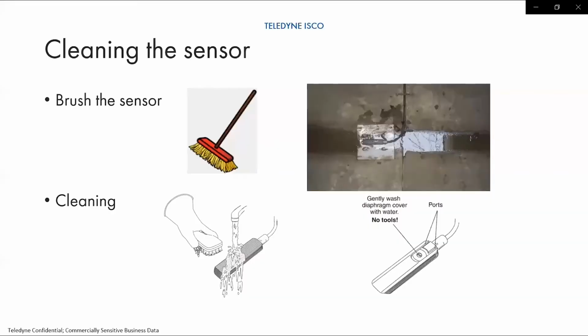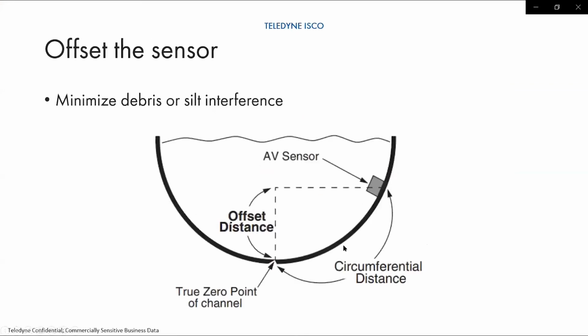Other cleaning techniques, I see a lot of field crews essentially go out with a broom, or they fabricate a pole and put a broom head on there and just simply brush off the top of the sensor to clean that debris out of there. If you do remove the sensor, usually just use tap water, and try not to touch the sensor directly, because usually it's just like a thin aluminum shield that's filled with oil, and you don't want to damage the actual transducer, but just run some tap water over the top of it, usually to clean the sensor.